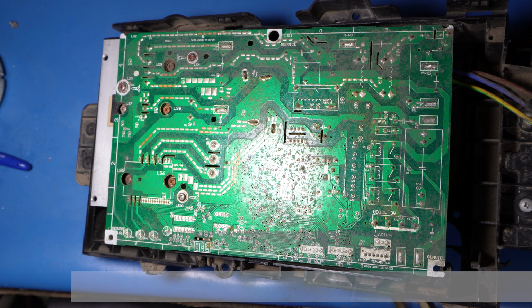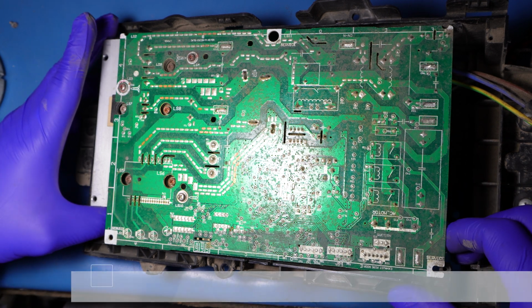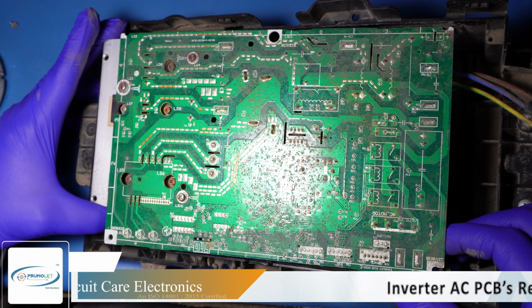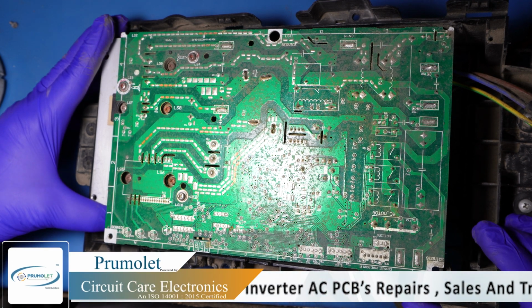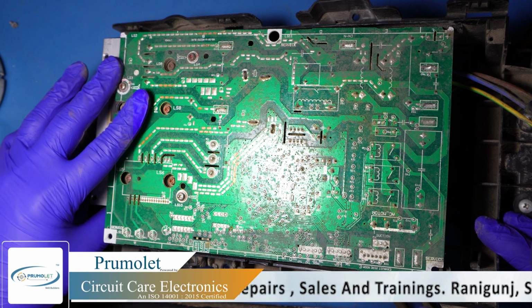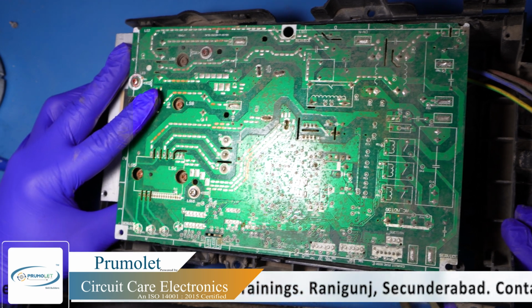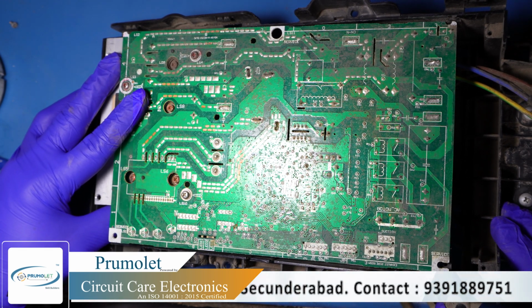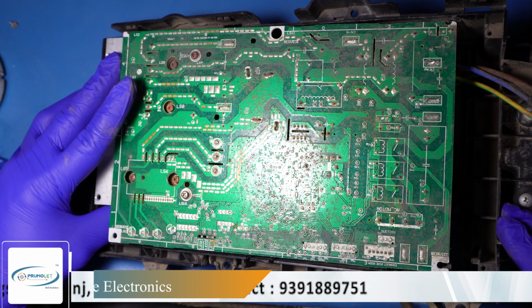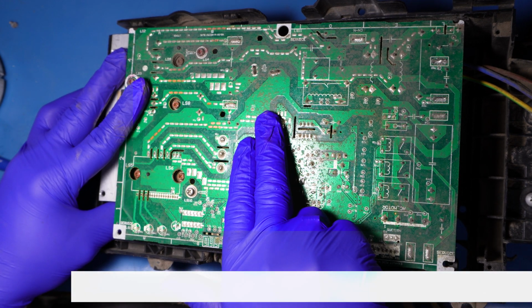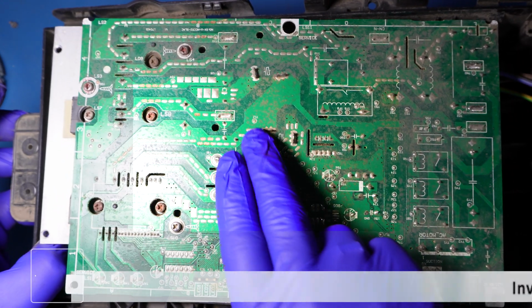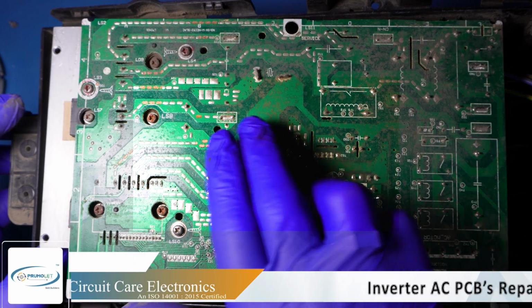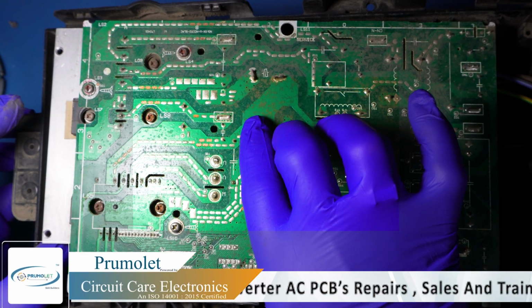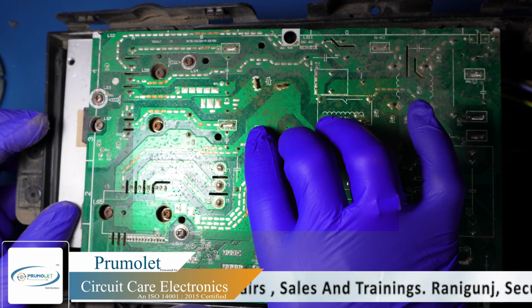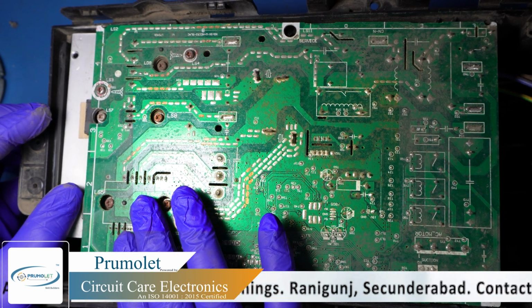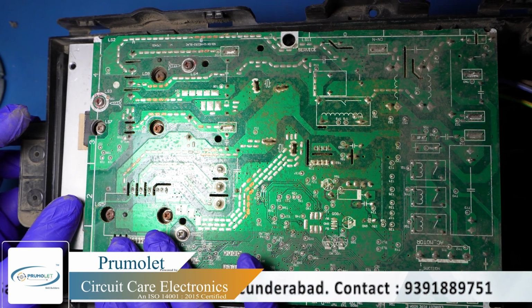Why the PFC overcurrent is coming: the power factor correction circuit works based on two factors. One is the voltage at these capacitors, and another one is the load of the compressor.